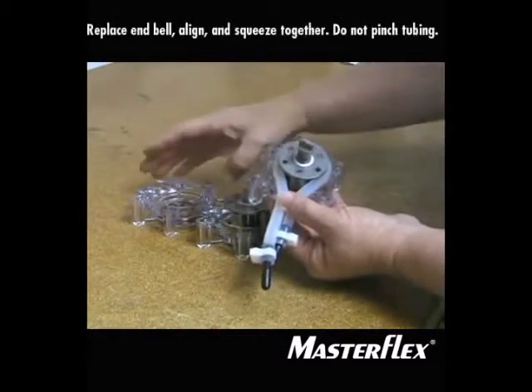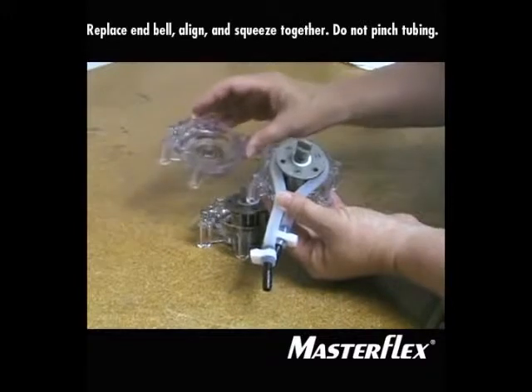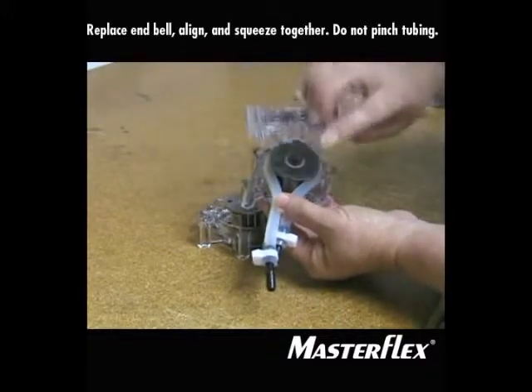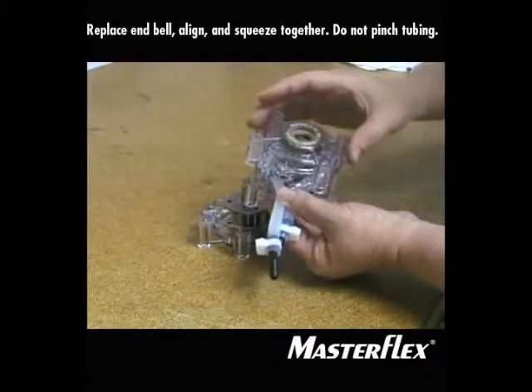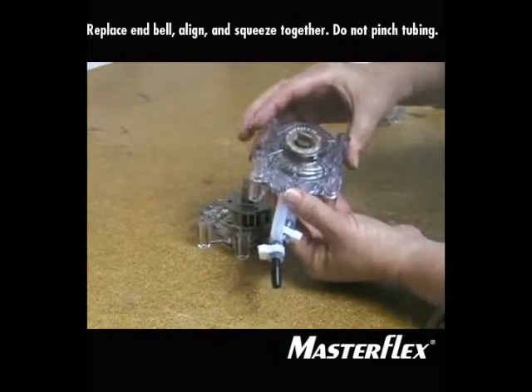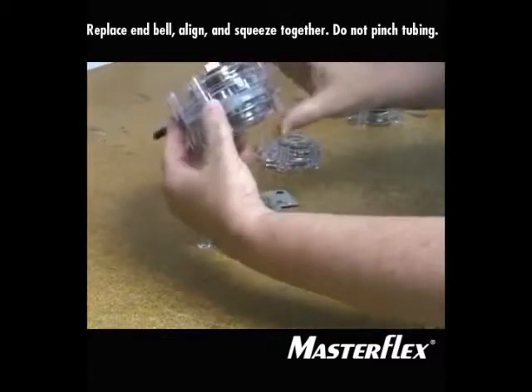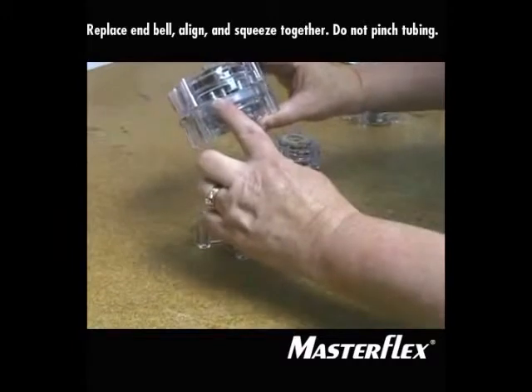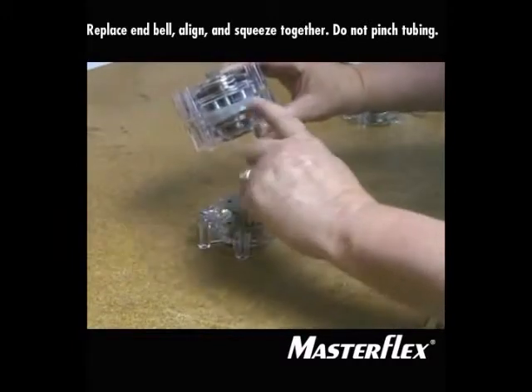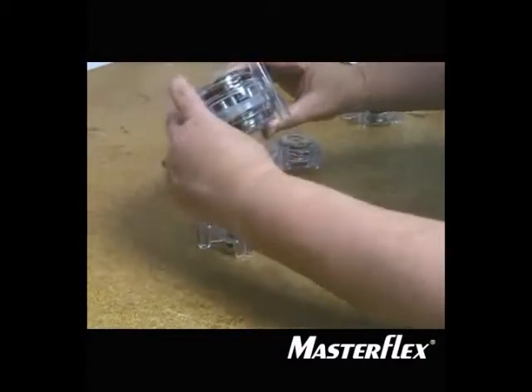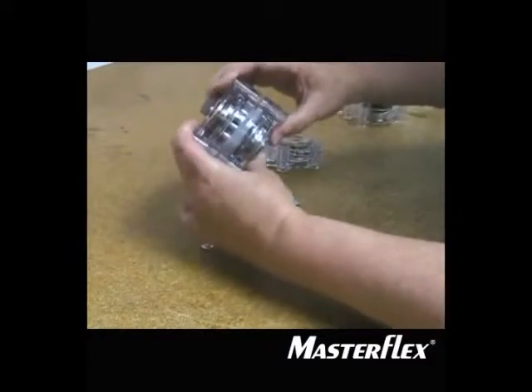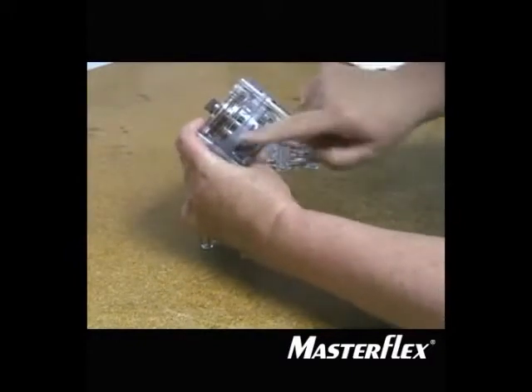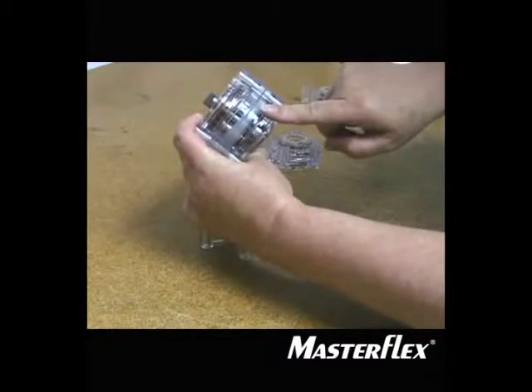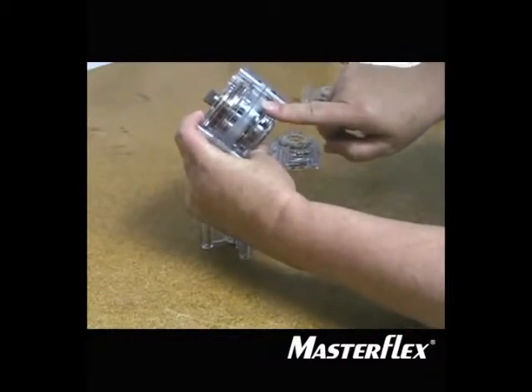Now I'm going to replace the other side of the end bell, like so, and line it up. I'm going to squeeze the two halves together, all the while watching to make sure I don't pinch the tubing between the halves. Notice how the tubing is now in the center of the pump head.